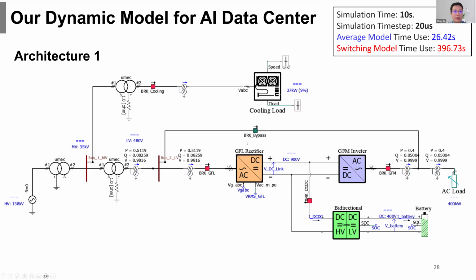We can change the control mechanism for the rectifier to also regulate the grid side voltage, especially if we have a battery - we could use the battery to supply power support for the power grid. But in general, I don't think data centers are doing this. What they want is to use the battery to supply their AI computing load; they are not currently using the battery or UPS to support the grid. But technically, yes, we can use the rectifier to regulate the grid side voltage.